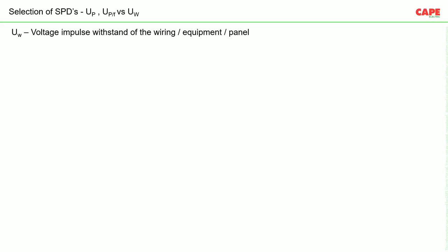Now, selection of SPDs on the basis of voltage protection level, and how voltage protection level is dependent on the wire length. There are three parameters: UW, UP and UPF. UW is the voltage impulse withstand of an equipment. Let's say I am talking about a UPS. Every equipment has a certain voltage impulse withstand capacity. It can be 1.5 kV, 2 kV, 3 kV or anything. But they will mention this UW in their data sheets and parameters.